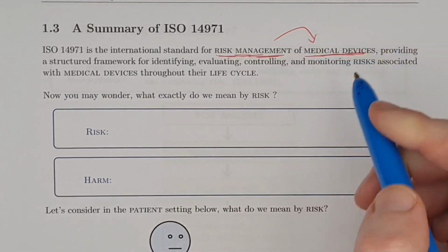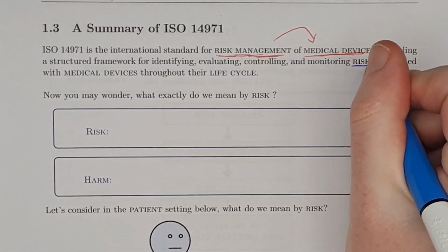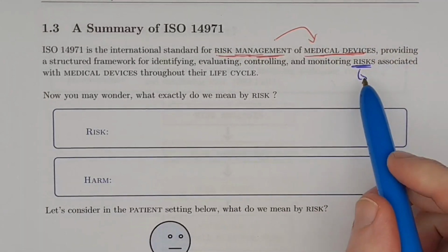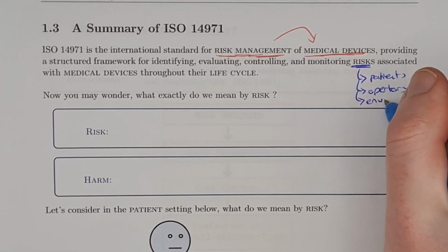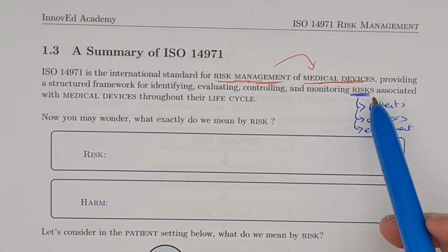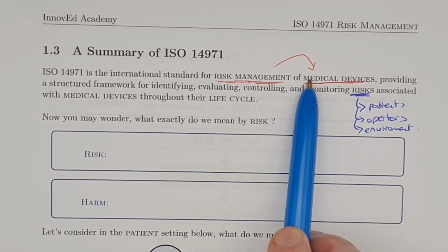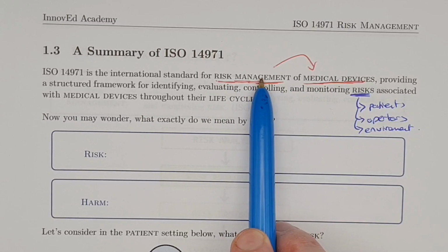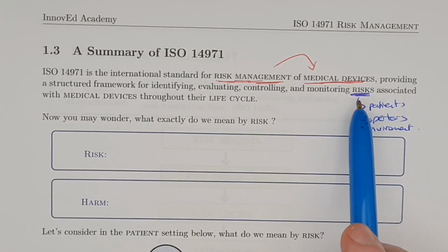And what does that mean when we apply risk management? Well, that means the risks that we're going to end up talking about are going to be risks that relate to harming patients, operators, and the environment it's used in. So you still consider things like fire hazards, but you don't consider things like business risks, because you can, of course, apply risk management to business and then you have financial and schedule risks. But here, of course, we're talking about medical devices, hence the standard adapts risk management principles to medical devices. So we narrow our focus of the word risk to just these three key areas.